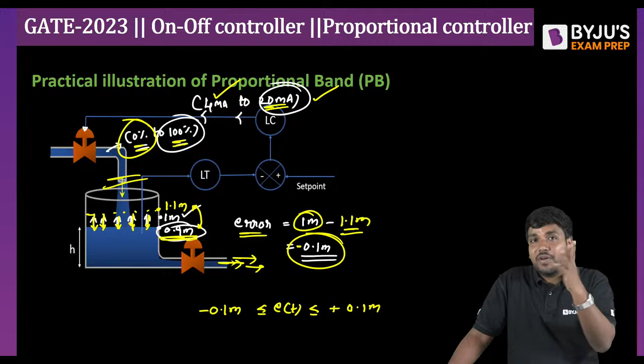Clear? Excellent. Very good, Shivani. Excellent. It oscillates between 1.1 meter and 0.9 meter continuously, right? You will never get 1 meter now. Okay, it continuously goes on cycling. And this was a question asked to me in the BARC interview. Clear? This is the reason why the proportional band should not be so small, right? If the proportional band is so small, it turns out to be an on-off controller. Clear? So that's the next concept, that is the on-off controller.